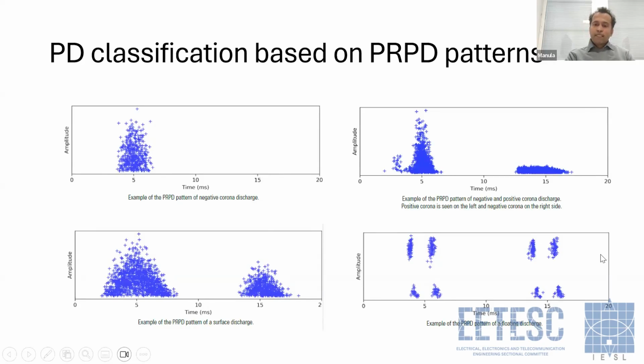And our fourth PRPD pattern is the floating discharge. The characteristic of floating discharge is that it would have peaky or impulsive types of clusters. It is not necessarily 2 clusters per half cycle. There might be 3 or a higher number of clusters depending on the type of floating discharge. So as a summary, based on the PRPD pattern, we can categorize them into different types of partial discharge. When we use acoustic cameras to detect partial discharges, we can correlate them to this AC waveform, and then we can distinguish what kind of partial discharge this is.